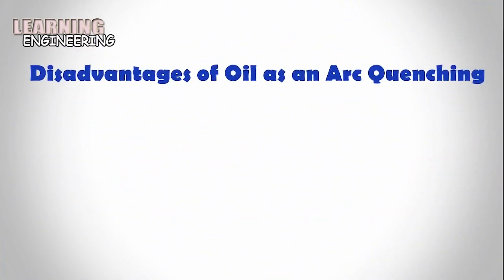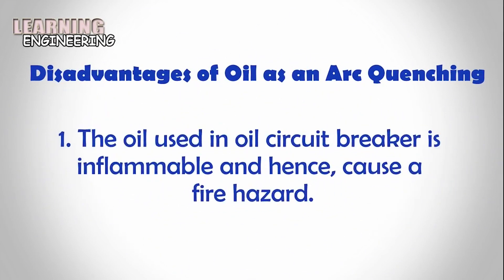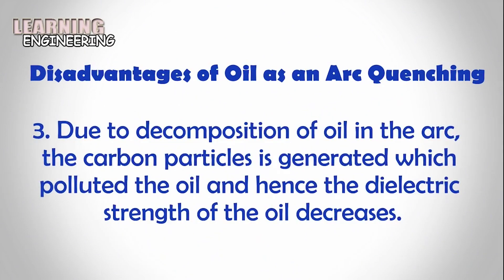Disadvantages of Oil as an Arc Quenching Medium: 1. The oil used in the oil circuit breaker is inflammable and hence causes a fire hazard. 2. There is a risk of the formation of an explosive mixture with air. 3. Due to the decomposition of oil in the arc, carbon particles are generated which pollute the oil and hence the dielectric strength of the oil decreases.